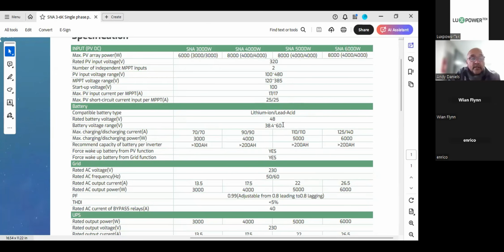For you guys that are installers, and especially for distributors that are monitoring and offering tech support, you will notice that on the maintenance, not on the maintenance page, the data history page, if you scroll across in all of the information that you get, in one of the columns there are 2 columns that show you the V bus voltage. V bus 1 is DC from the battery, and V bus 2 is DC from the PV array, okay? So typically we're looking for 7 times the voltage of the battery on V bus 1 in the 6 kilowatt. If it's a 50-volt battery, then we're looking for about 350 volts on the V bus 1. That's just some extra information.